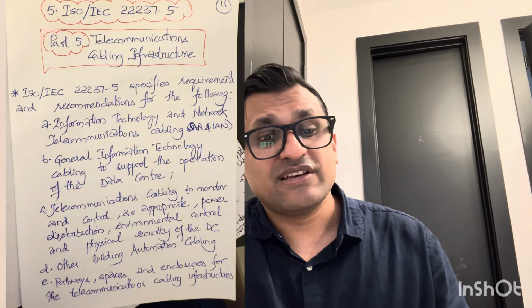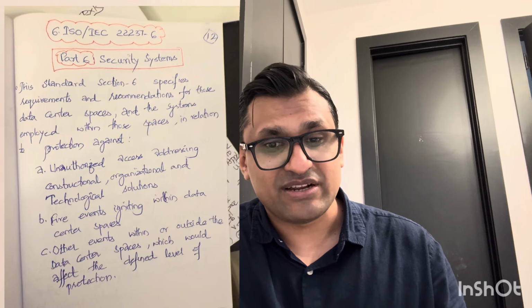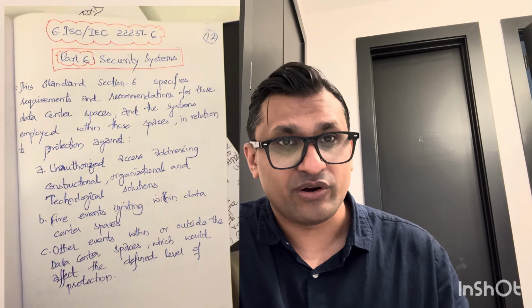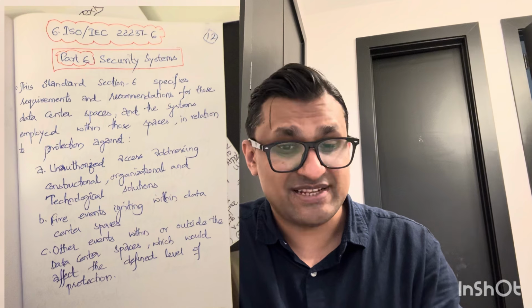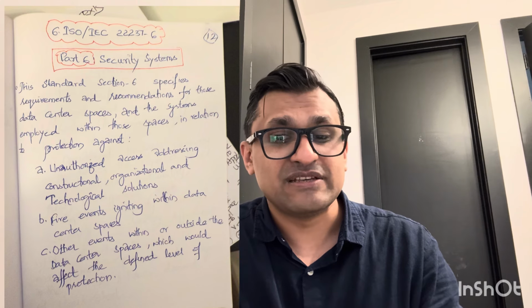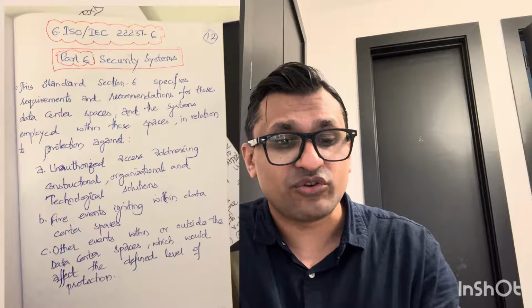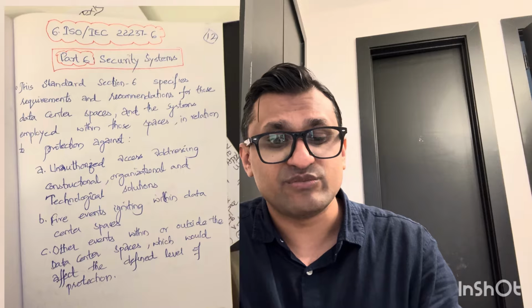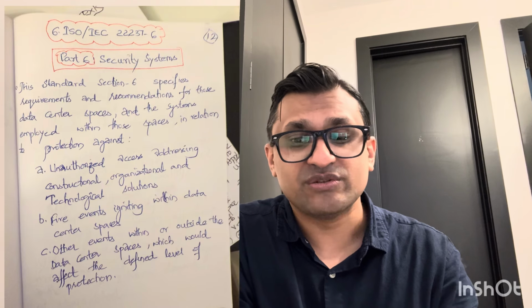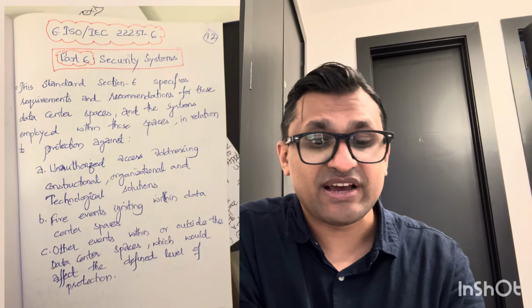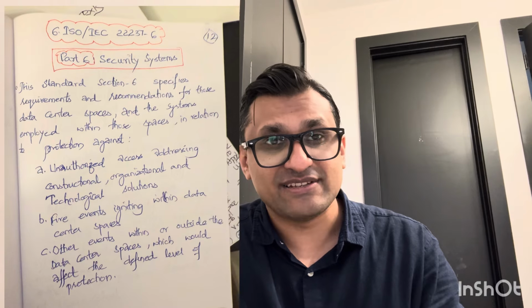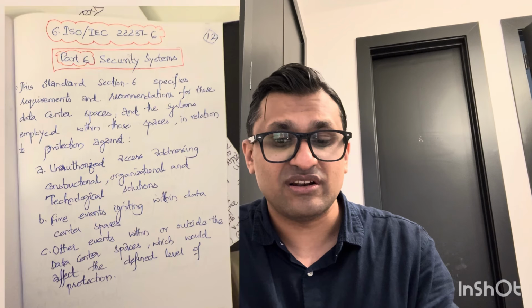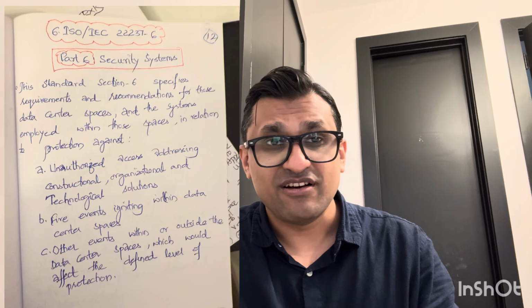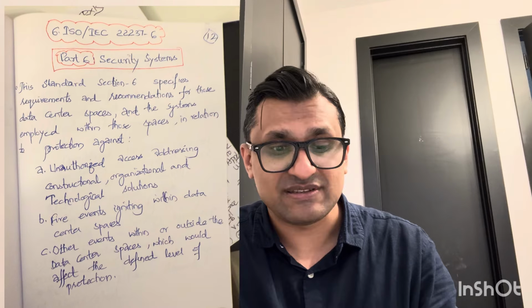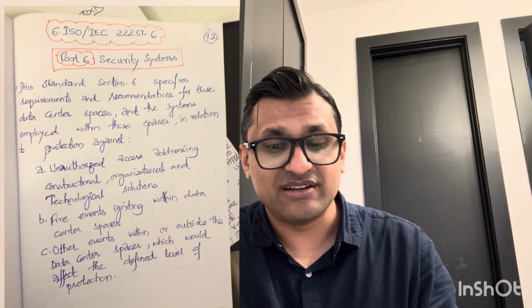Part 6, ISO 22237-6, is the security system needed in the data center. This standard specifies requirements and recommendations for data center spaces and the systems employed within those spaces in relation to protection against: unauthorized access, addressing constructional, organizational, and technological solutions; fire events igniting within data center spaces; and other events within or outside the data center spaces which would affect the defined level of protection.